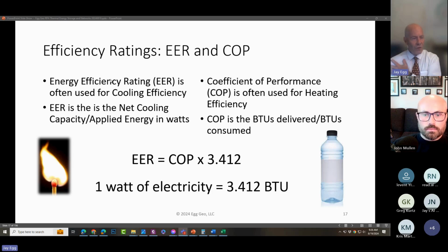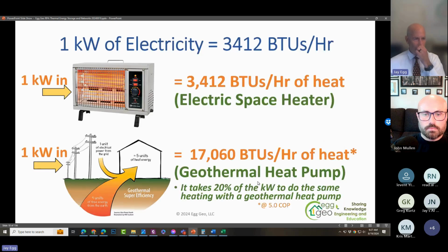Interestingly enough, air conditioners are often rated in EER, which is a different way of saying the same thing, but it mixes units. EER is the net cooling capacity divided by the applied energy in watts. And a quick conversion is EER equals COP times 3.412. And the conversion for that is very simple. 1 watt of electricity equals 3.412 BTUs. In other words, if you apply 1 watt of energy to 1 pound of water, it would raise it 3.4 degrees Fahrenheit. So understanding that, let's look at why heat pumps are all the rage.